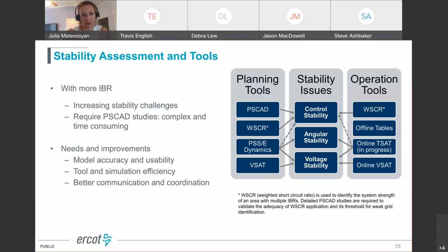We're also working on an online transient stability assessment tool, because we recognize that offline tables may introduce some inefficiency at times, but may also be overly optimistic because they are only geared to studied system conditions, and it's better if we consider real-time conditions during transient stability assessment. Currently in implementation is the TSAT tool in real time. And we do online voltage stability assessment every 10 minutes. This is where model accuracy and usability becomes really important, and there are a lot of efforts going on in ERCOT to improve accuracy and verification of dynamic models.